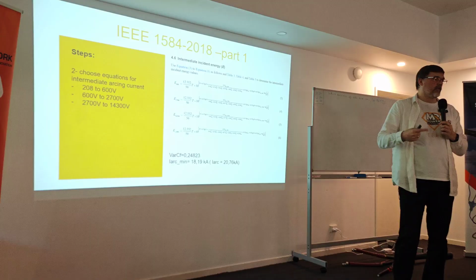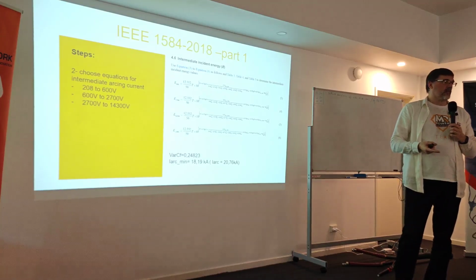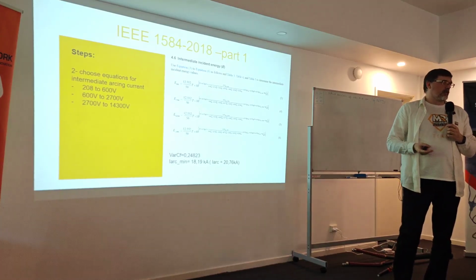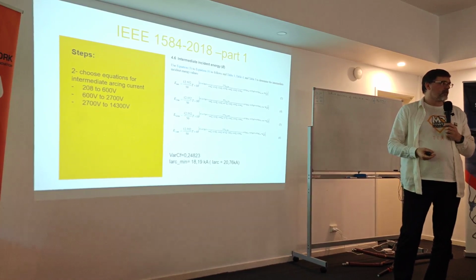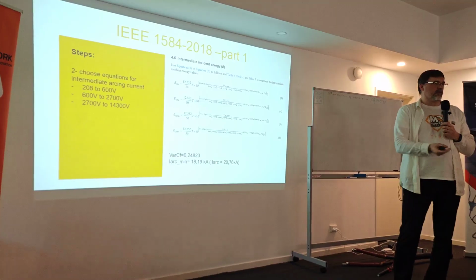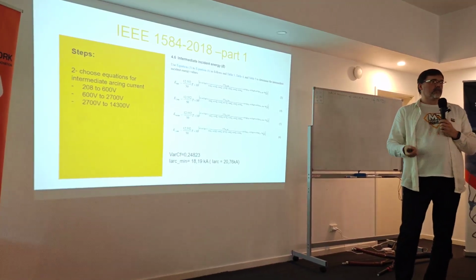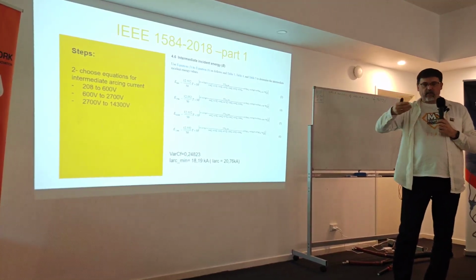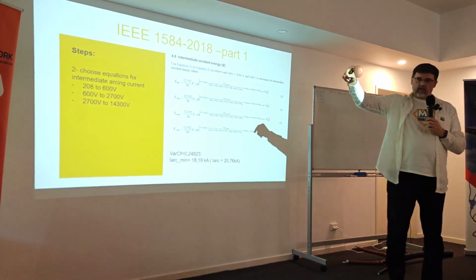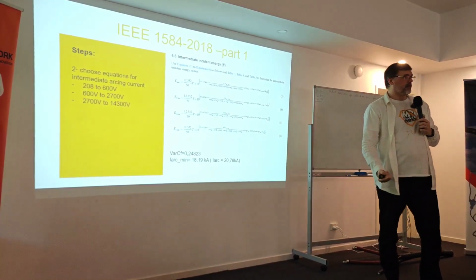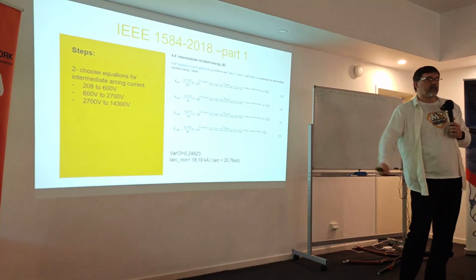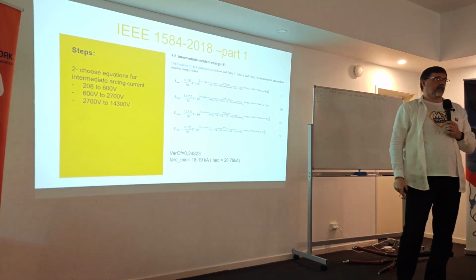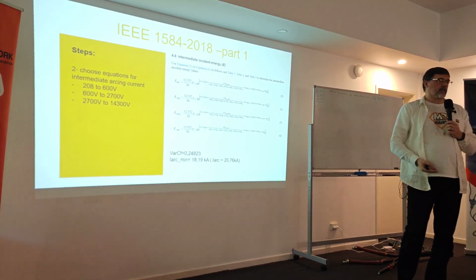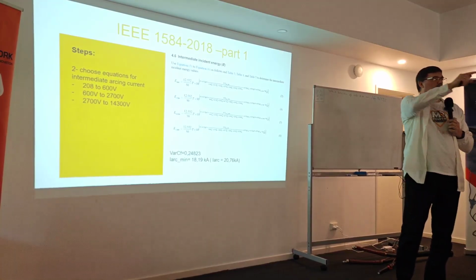And it's very easy to overlook things, because if you overlook things, you would just tell someone, yeah, it was 50 milliseconds. And then we check it and it's like, no, it's not. It's actually 2 seconds for you to trip here. And it's like, how? Because again, that's why the digital models are useful, because then you can see, no, because this part is not fed by 2 generators. It's fed from one side, but not from the other side. And that makes a huge difference for the short circuit current that you have to trip. It's also logic how the things work.